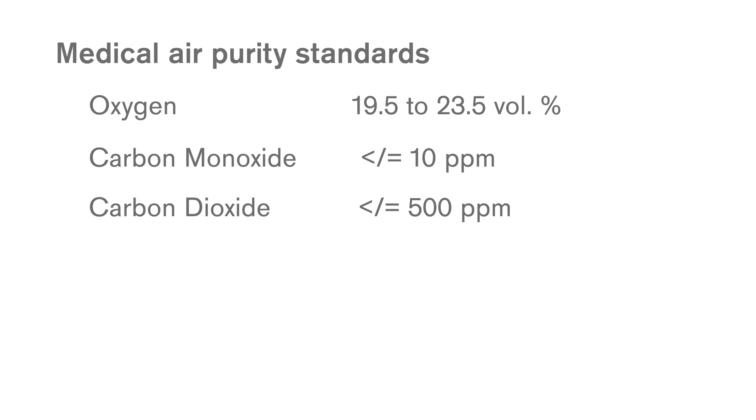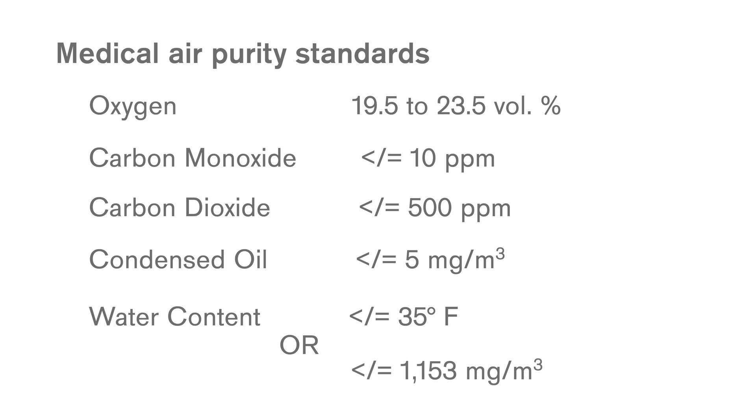The medical air purity regarding oxygen is 19.5 to 23.5 volume percent. Carbon monoxide, less than or equal to 10 ppm. Carbon dioxide, less than or equal to 500 ppm. Condensed oil, less than or equal to 5 mg per cubic meter. And water content, 35 degrees Fahrenheit or less than or equal to 1153 mg per cubic meter. Please confirm the limits with the most current standard.